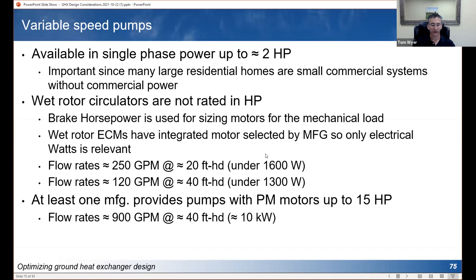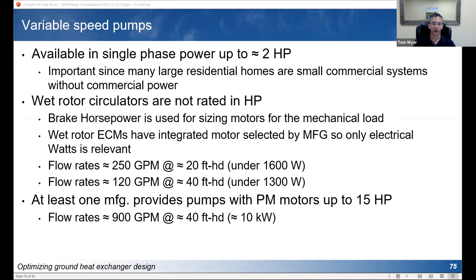One manufacturer provides permanent magnet motors up to 15 horsepower, with a pump that can do 900 GPM at 40 feet of head. So if you keep your head loss low as described, it's really simple to select a pump that will give you an A rating on watts and keep a building owner happy.